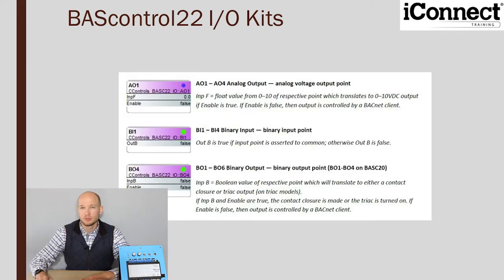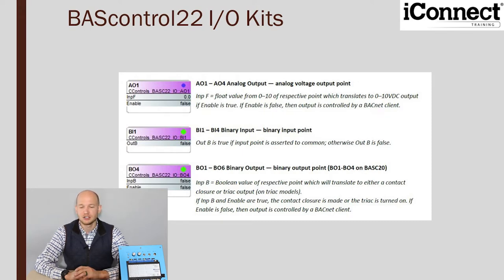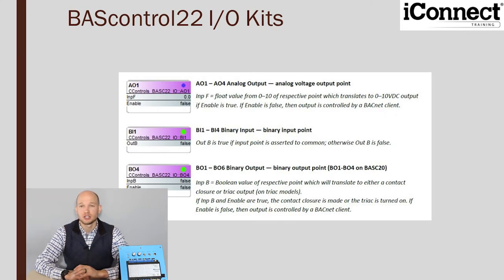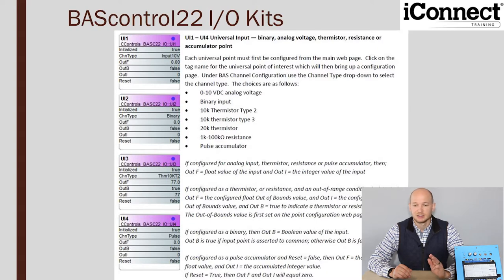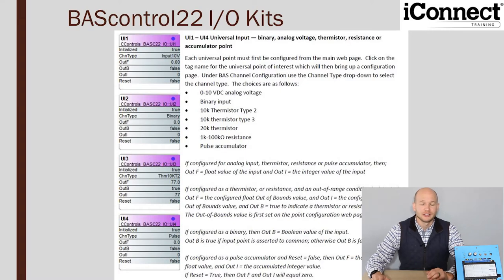Taking a closer look at the analog and binary inputs and outputs — what you see on screen are the individual components. When you select a component and drag it to the wire sheet, this is what you're going to see. The universal points have a wider range of usage: we can utilize them for analog voltage, binary input, thermistors, resistance, and accumulators. There's a very wide range for the universal points.